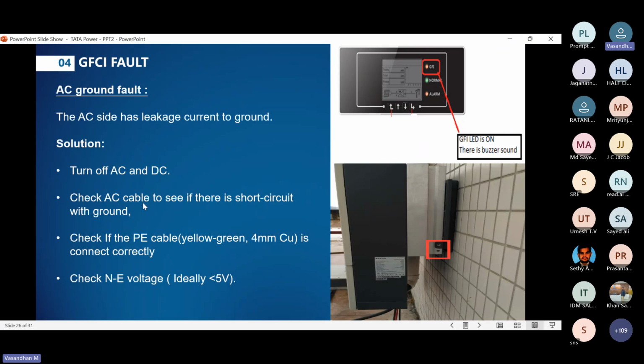Check the AC cable, whether there is any short circuit with the ground or not. Check the PE cable, the yellow-green 4 mm copper cable, whether it is connected properly and tightened properly or not. Check the neutral to earth voltage, it should be less than 5 volts. All these you can take a photograph of for future reference. So it will clear easily by yourself.